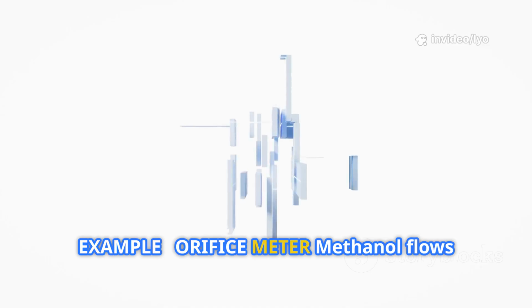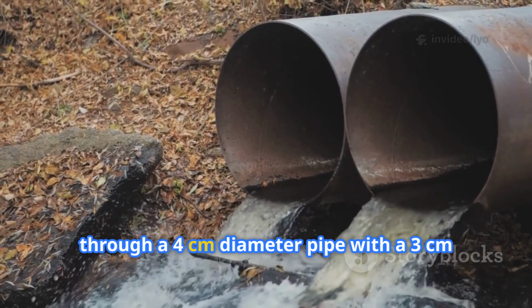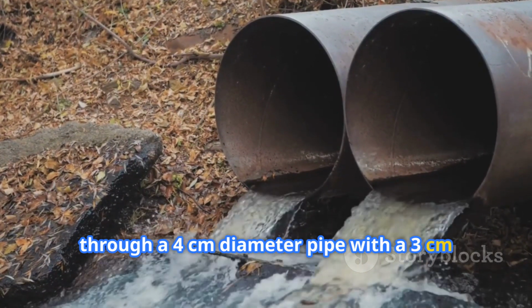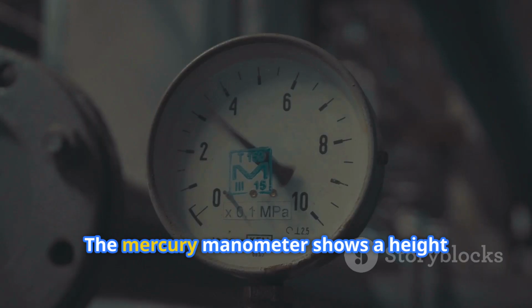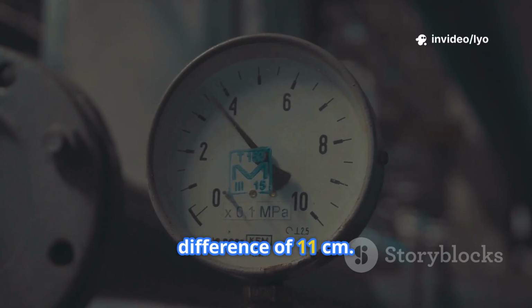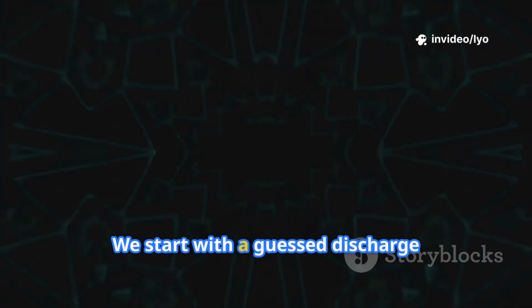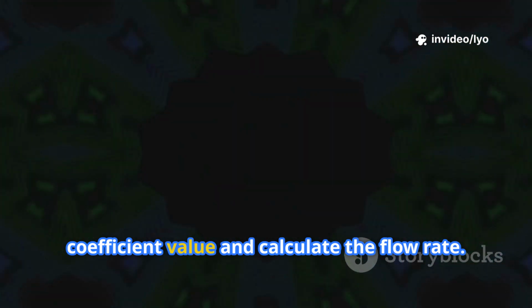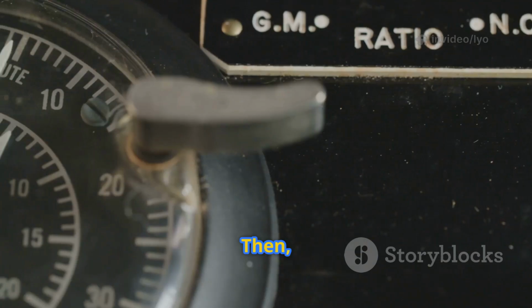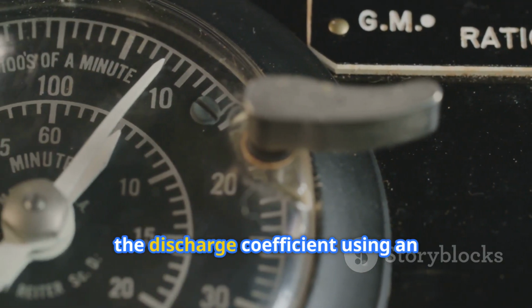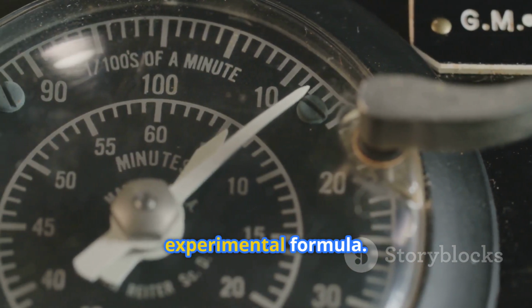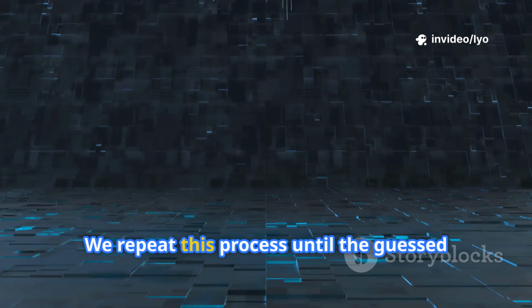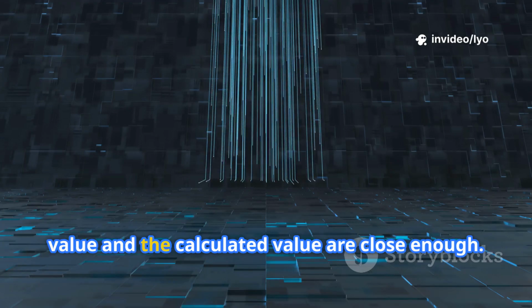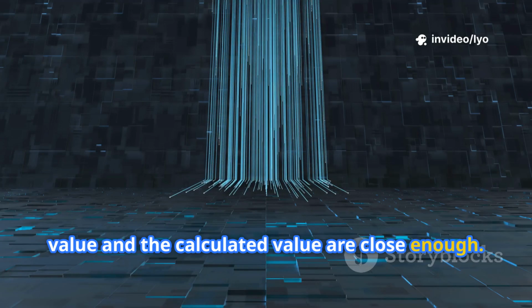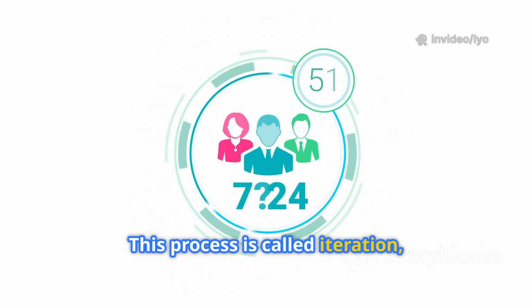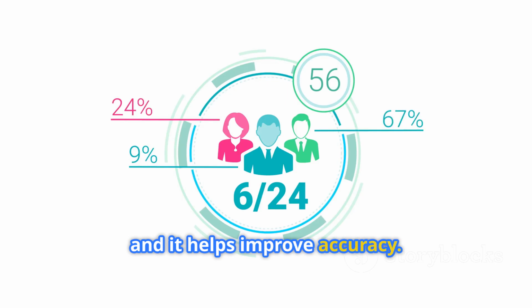Example: Orifice Meter. Methanol flows through a 4 cm diameter pipe with a 3 cm orifice plate. The mercury manometer shows a height difference of 11 centimeters. We start with a guessed discharge coefficient value and calculate the flow rate. Then we find the Reynolds number and update the discharge coefficient using an experimental formula. We repeat this process until the guessed value and the calculated value are close enough. This process is called iteration, and it helps improve accuracy.